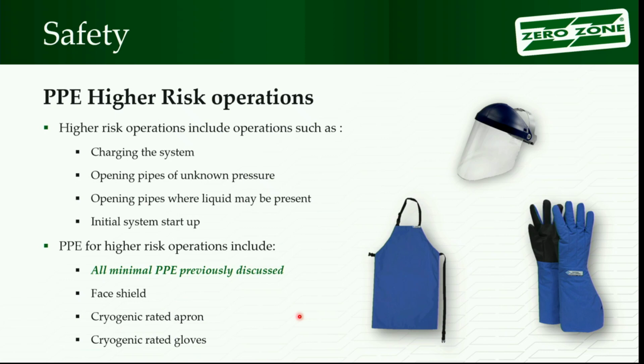Then we talk a little bit about higher risk operations. If you're charging the system, you've got more liquid available. Hopefully everything's connected right, but maybe sometimes it isn't. Maybe a line cracks or breaks on you and starts spraying some liquid CO2 out. Having additional safety equipment on would be a good thing to have. So that's where you get into the face shield.